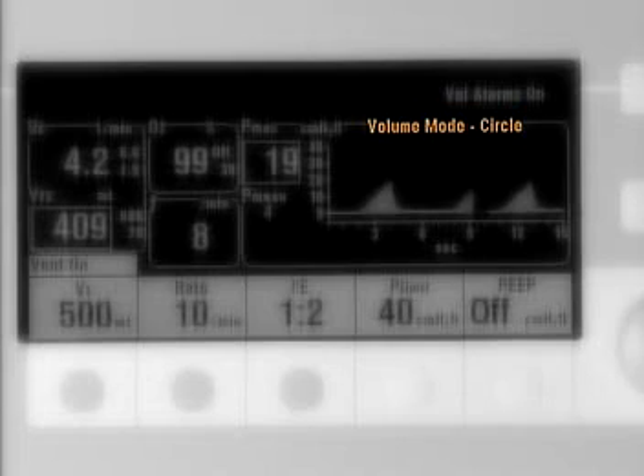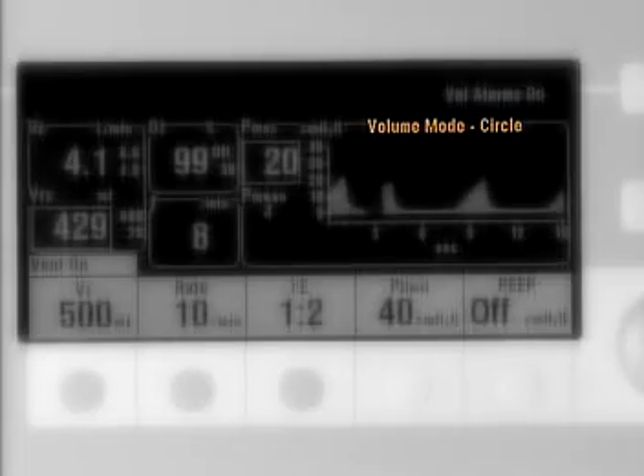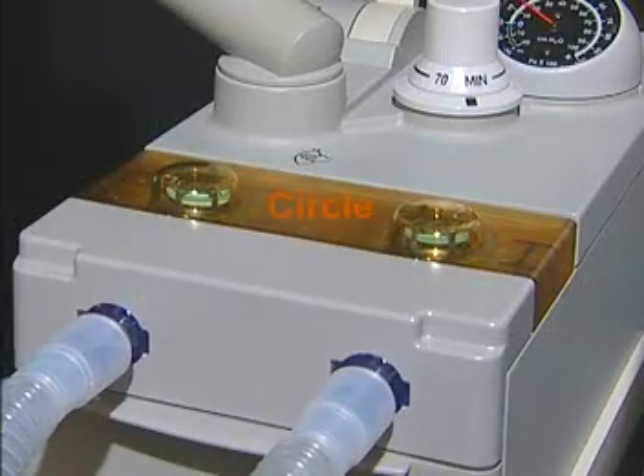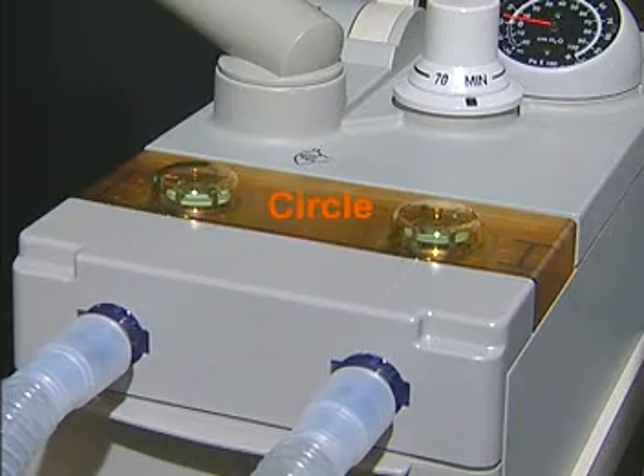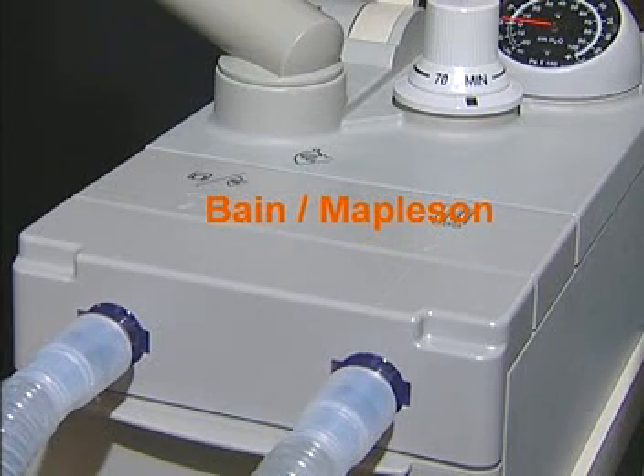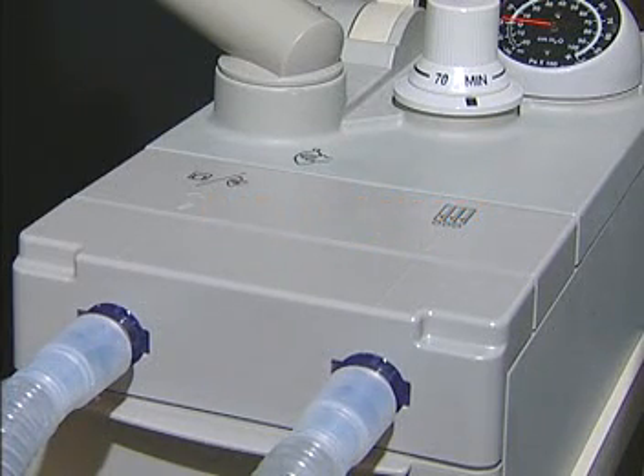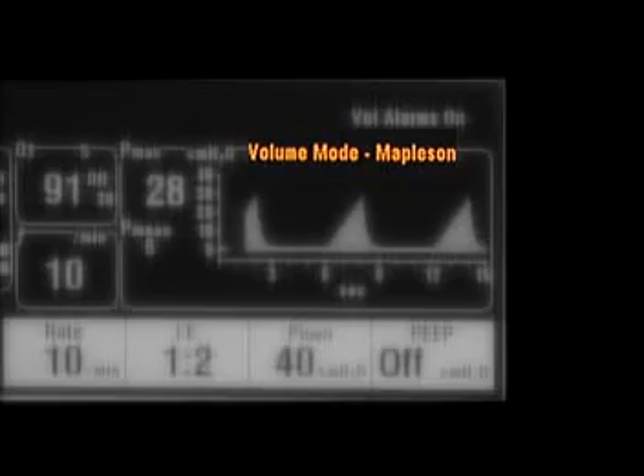Above the ventilation waveform, an area has been dedicated to indicate the ventilation mode chosen and the circuit module that is in place. Two circuit modules are available. A circle module is standard. A Bain module is optional. The Bain module blocks out the absorber, has no check valves, and changes the software so that fresh gas flow during exhalation is not reported as delivered volume.